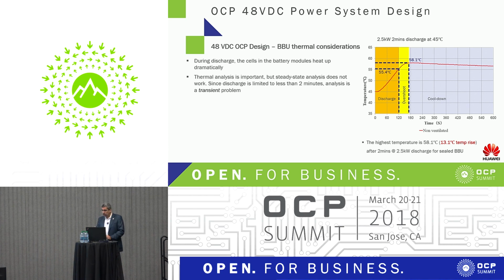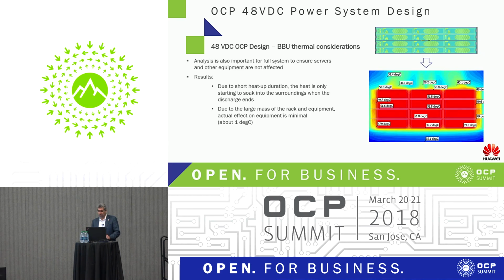But this actually is all within spec. We go up to 58 degrees. Again, remember, we're starting at 45, that's already worst case scenario. We go up to 58 degrees, and then we cool off from there. So that actually works perfectly well within the operating parameters for the batteries.